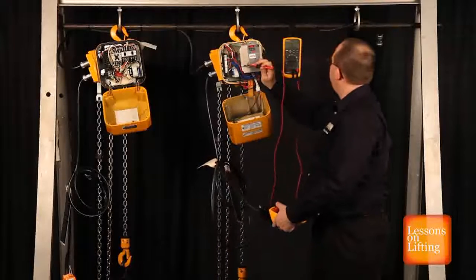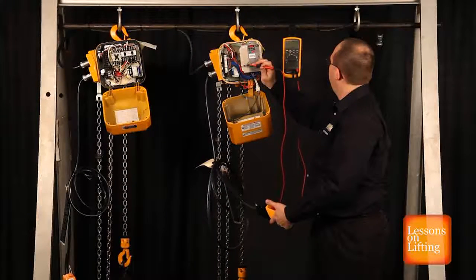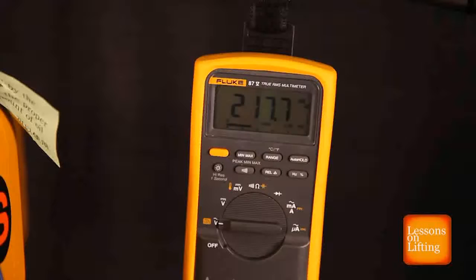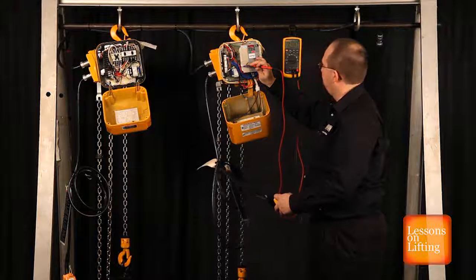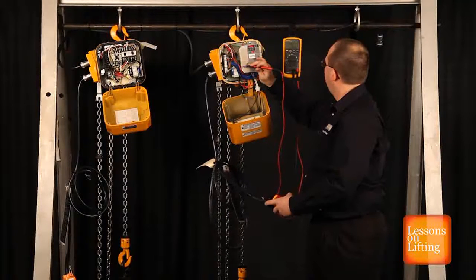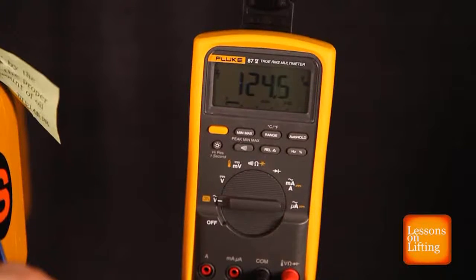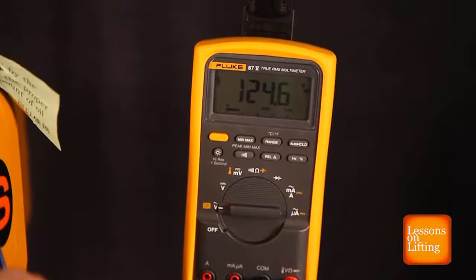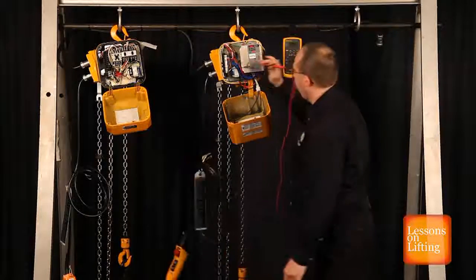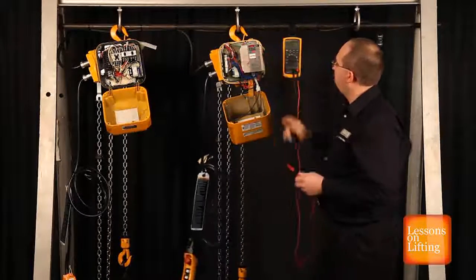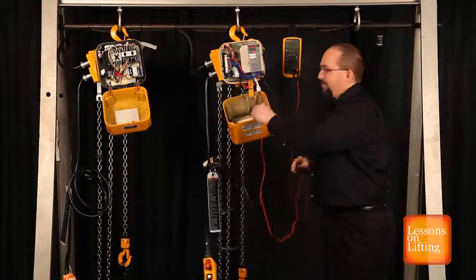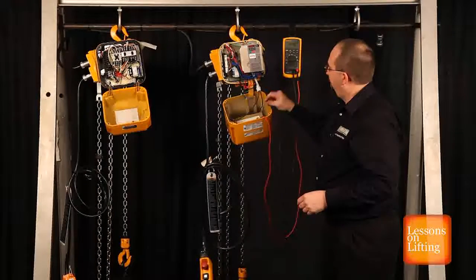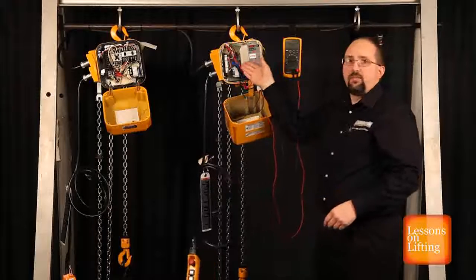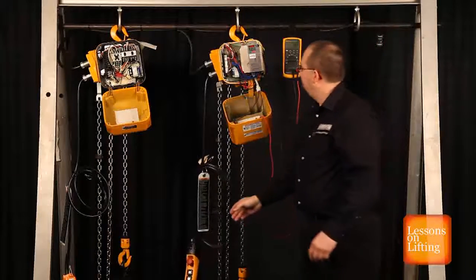We can also test the E-stop while we're here. With the E-stop button pushed, we're down to millivolts, okay, 200 millivolts. Basically, it's an open circuit. With the button released, we have 124.8 volts. All right, so now we know that that's all good. The next step is to verify that the relay on the interface board is good.